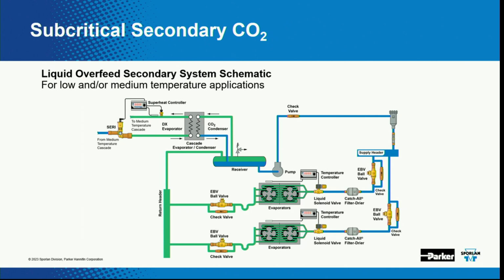This one's just a DX subcritical secondary CO2 system. All we're doing is using DX on the left, and pulling the vapor through the subcooler on that fan frame. As you pull that gas from the receiver, you turn it into liquid at the bottom, liquid sits at the bottom, and you just recirculate the pump to the cases.